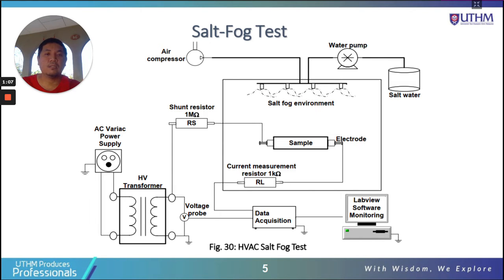Okay, so this is basically the setup or the arrangement for the salt fog test. We have the sample in the middle. This is the dielectric material or the insulation that we want to test, right? And you can see here we have a spray nozzle to supply salt fog within this chamber. So the insulation is kept inside the chamber, and the nozzle will give that salt fog. Then we have a high voltage supply connecting to the electrode here, and this other electrode will go to the ground.